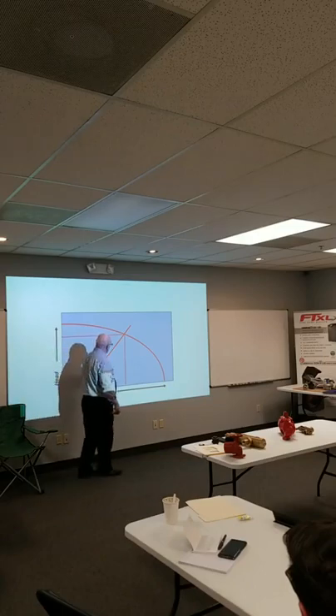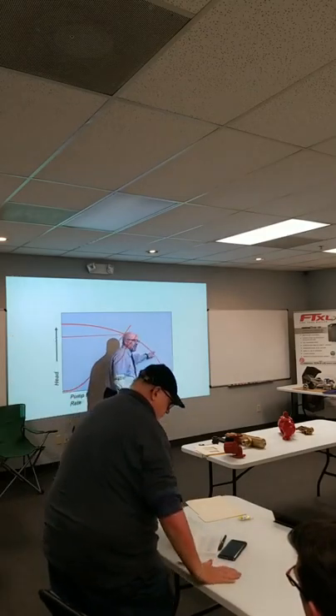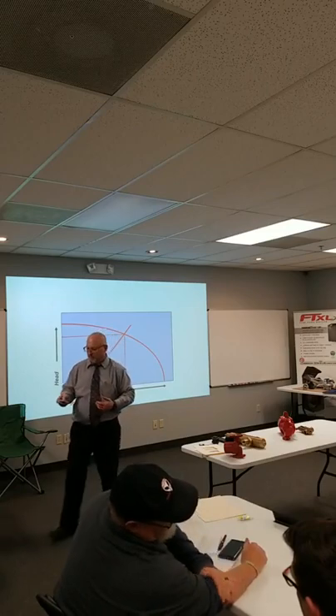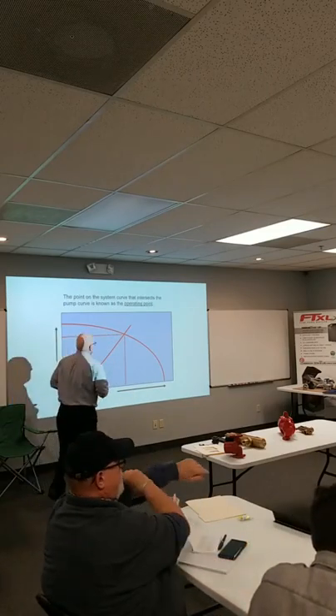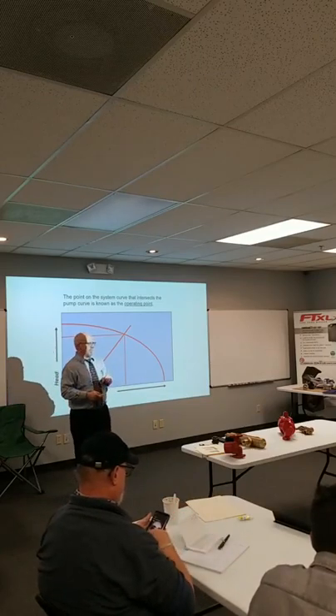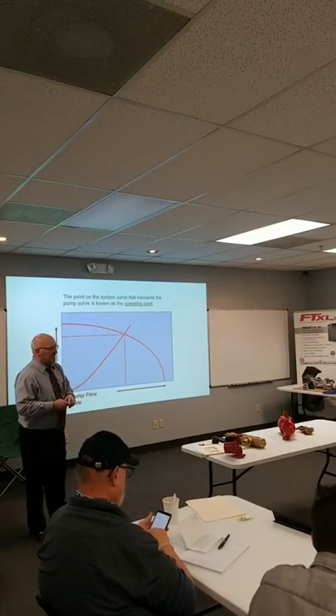So if my system resistance curve has less resistance and it's down here, then that's when I start to overload my horsepower. That's why we got to create that resistance to bring it back. But it's higher flow. The higher the flow, the lower your head. The higher the flow, the more resistance in the system. But the higher the flow, the more heat you're moving.